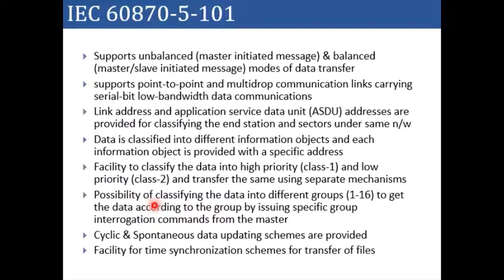In 101, there is a possibility of classifying the data into different data groups. So typically 1 to 16 data groups you can create. This will create different data groups to get the data according to the group by issuing specific group interrogation commands from the master side.